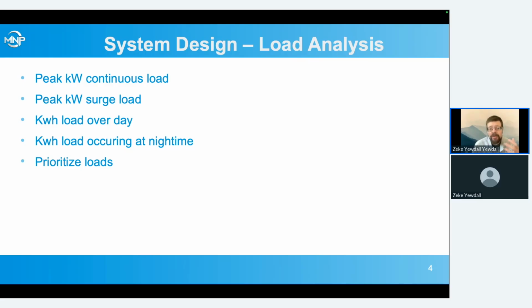It can be difficult to get all this information, and the tendency I see a lot is to say, I've got a 2,000 square foot house. Is one inverter enough? Yeah, you might as well ask what color is the trim around the windows. It's almost as relevant as the square footage of the house. I've seen a 600 square foot house that had loads way too heavy for one inverter and one or two batteries. And I've seen a 3,000 square foot house where one inverter and two batteries would provide a very nice backup power system. It really depends on what kind of loads are in there and what kind of pattern of operation you have.